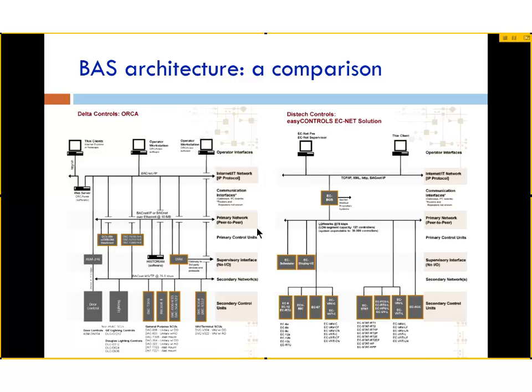Now, as you go down in the network architecture, you'll see that you get to a peer-to-peer level where you have the supervisory controllers, and it's running BACnet over Ethernet. That's just communicating between the controllers themselves using Ethernet as the media. And below that, you have a secondary network, which might be master-slave token passing BACnet, or it could be something else running at the RS-485 level, where each air handling unit would have its own controller that is on that network, the secondary network in the Delta Controls architecture.